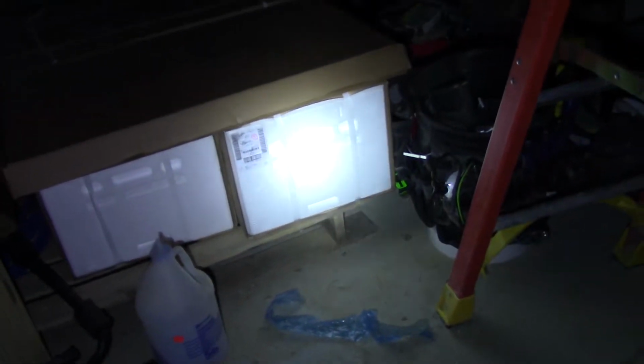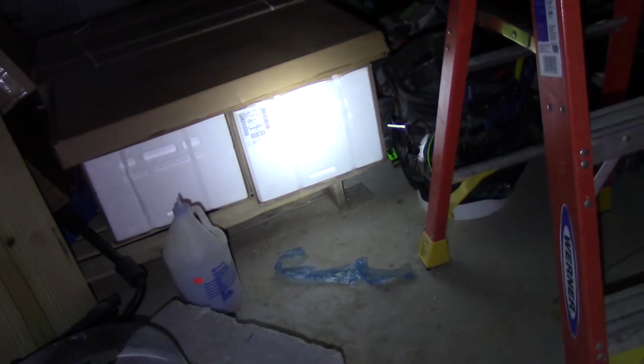Our setup is going to be two of these ductless split units, Mitsubishi Hyperheats. One of them is a 12K BTU, going on the wall here for the basement. Then there's a 6K BTU for the office upstairs, so we don't have to run ductwork into that room, and so it can be on a separate zone.